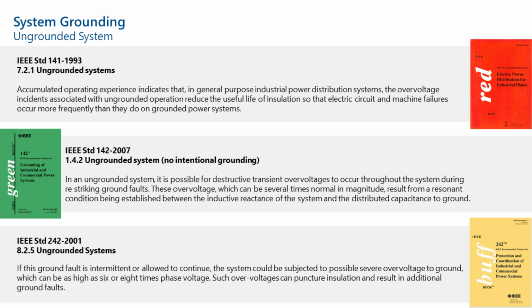For this reason, the NEC says that if you have an ungrounded or a resistive grounded system, you have to use higher insulation cable depending on the length of time your ground fault is on the system. If your ground fault is on the system between 1 minute and 1 hour, you have to use 133% rated cable. If your ground fault is on the system for beyond 1 hour, you have to use 173% rated cable, but that only occurs above 5,000 volts, not 5 kV, but 5,000 volts.